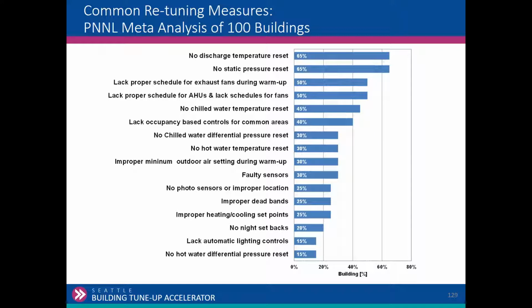Building static, and that's an interesting thing, because I trended static on a building one time. At 6 o'clock at night, when the system went down, it would always go negative all night. It would run negative pressure all night, and then the next day it would come up in pressure. So the exhaust fans weren't shutting down at night. They were running 24/7, basically. But through trending building pressure, we were able to see that the exhaust fans were running at night.